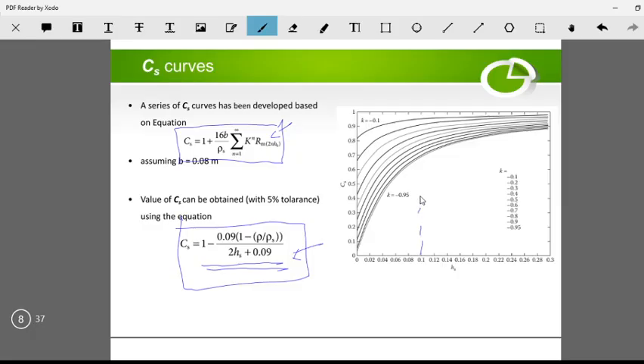For example, if you go here, and if k equals 0 to minus 0.1, then you have the derating factor of this much. If k equals, for example, 0.2 or 0.3, you can find the corresponding derating factor using this graph for your design purpose.